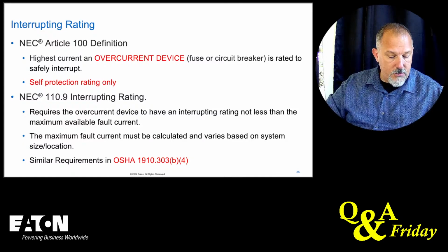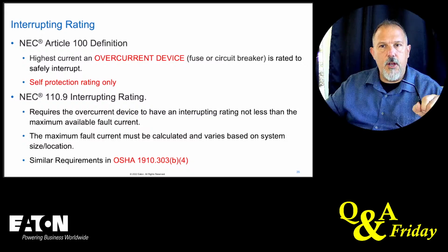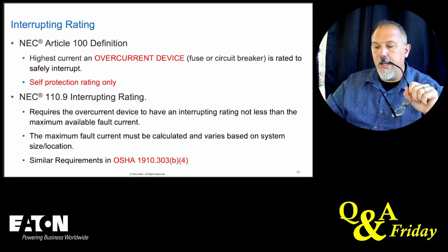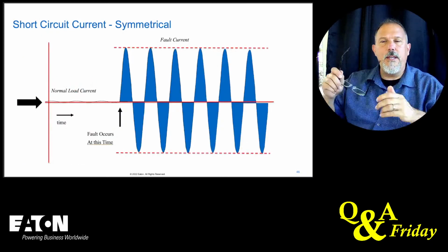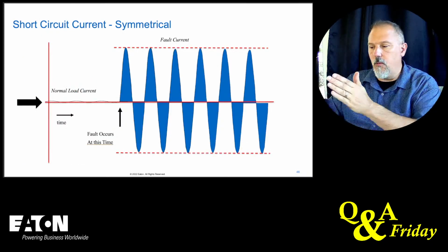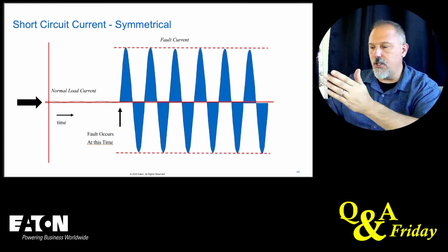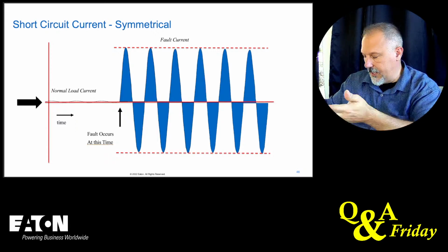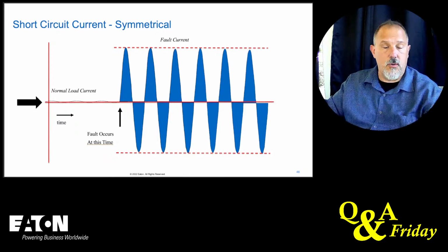So when we talk about the impact of ratings and voltage, voltage is pressure. One of the items that you have to think about when we compare an interrupting rating: when we do short circuit calculations, we calculate these types of currents. We calculate a symmetrical short circuit current.